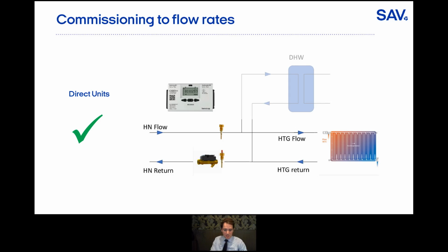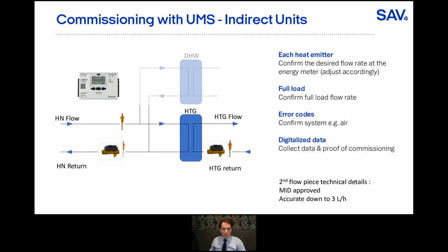The difficulty comes when we move away from direct units. When looking at indirect units, all of a sudden you have a plate heat exchanger separating out that heat network side from the secondary heating side. All of a sudden you're blind. You don't know what's happening in that space heating circuit. You've got a pump, you've got pressure independent control valves, you've got the different radiators, you have bypass radiators, towel rails, etc. You need to know what's happening to make sure you can commission and verify properly.